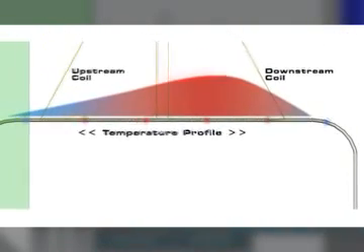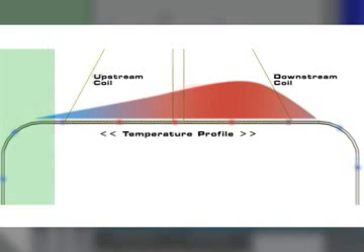This shift in temperature shifts the coil resistance and is measured by the RTD. The relative cooling of the upstream coil and the relative heating of the downstream coil create a difference in the resistance of the two RTD coils.